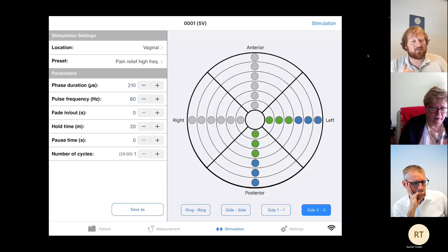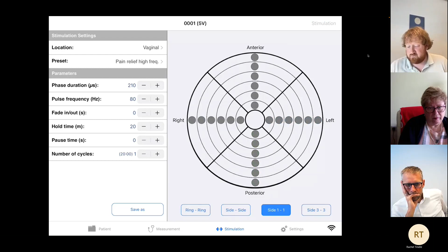There are 4 ways to actually give electrostimulation through the body via the probe. Because we have 24 electrodes on 6 sides, in 4 sides and 6 depths, you can very precisely stimulate different areas. What you would normally have with a bipolar probe is from ring to ring. We have that setting as well, but you have the option to select different depths for much more precise stimulation. We have side to side, like you would have with a bipolar probe. You can also stimulate in a quarter, so more precise. And then we have side 1-1. You can select on one side, very specifically between the electrodes, or on 2 sides as well. And then you go from deep till shallow and in between. And you have side 3-3, where you select 2 plates and go from shallow to deep.